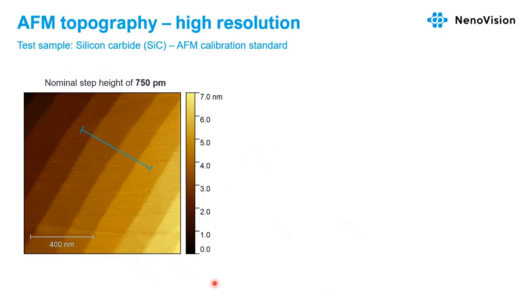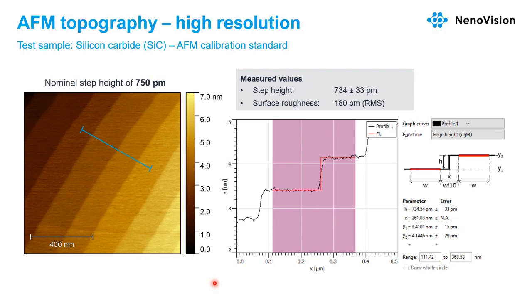I have an example of a high-resolution measurement. It's a silicon carbide sample. It's an AFM calibration standard. And so this sample has a nominal step height of less than a nanometer, and we were able to measure this Z step. And so we are at the limit. So we measured the step height of these terraces.